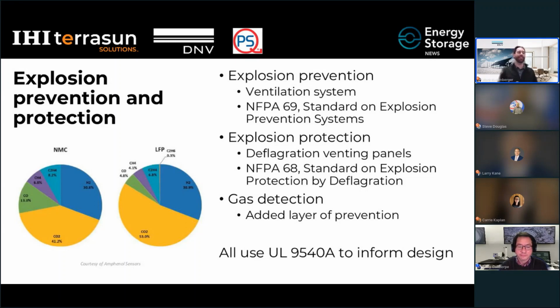On the other side, explosion protection can involve deflagration venting panels. To evaluate the effectiveness and need for these panels, we need to know how an explosion can evolve within a container and the pressures it can generate within the enclosure, which allows us to effectively evaluate the location and size of deflagration venting panels within the container.